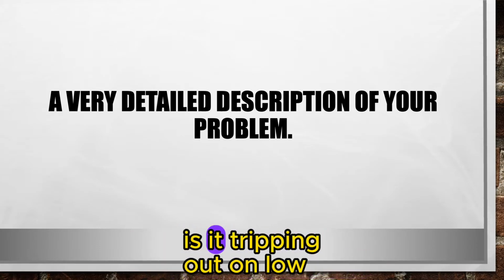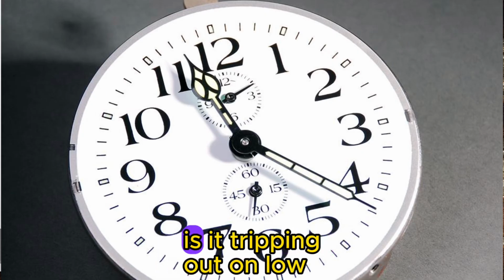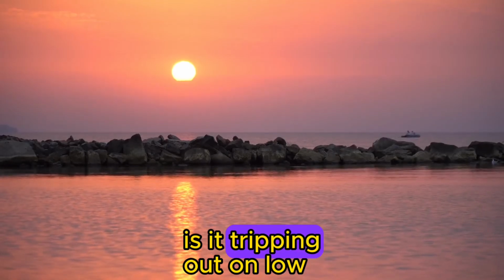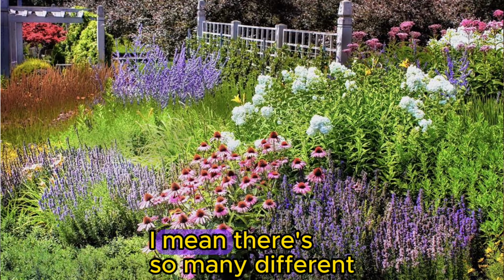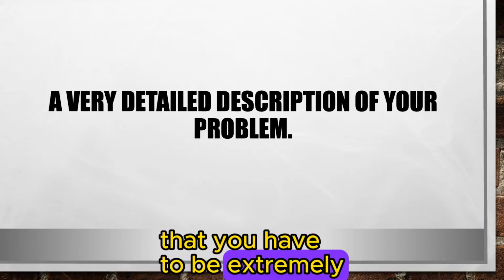He has no idea. Is it tripping out on low pressure after 5 minutes? Is it tripping out on low pressure overnight? Is it tripping out on low pressure over the weekend? Is it tripping out on low pressure once a year? There are so many different things you have to be extremely detailed about.